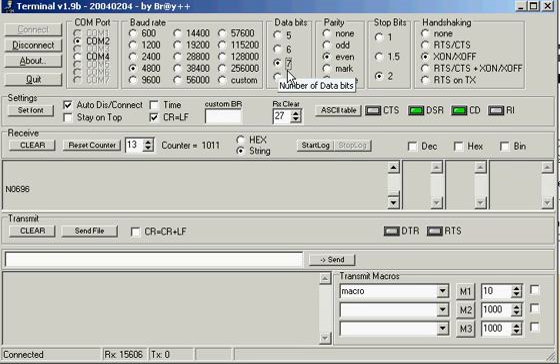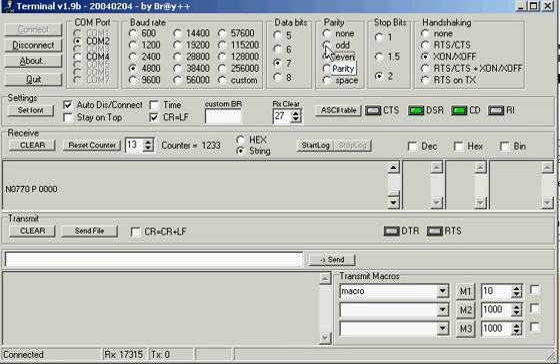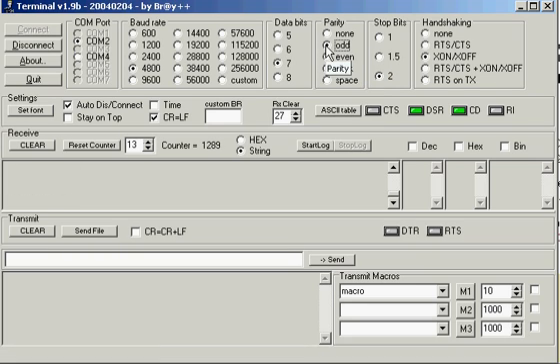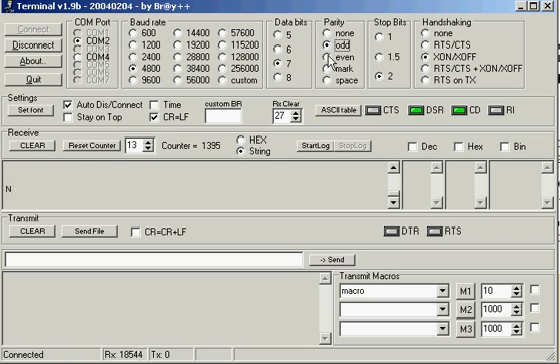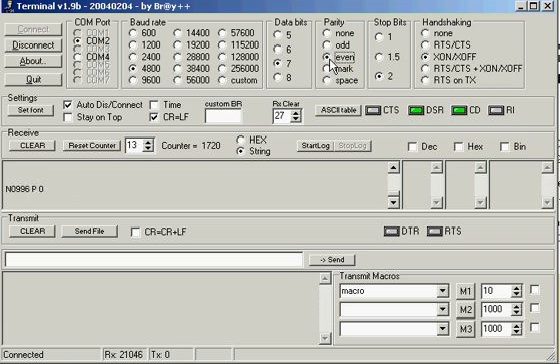Parity is supposed to be even as well. But if you play with the parity, notice that parity has little effect when you're actually receiving the data. Now, if that was incorrect sending the data, then you're going to have oftentimes a parity error on your control.